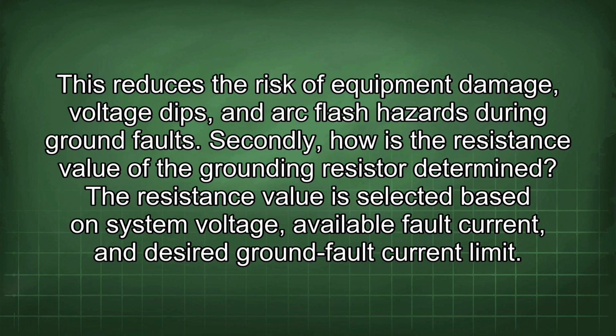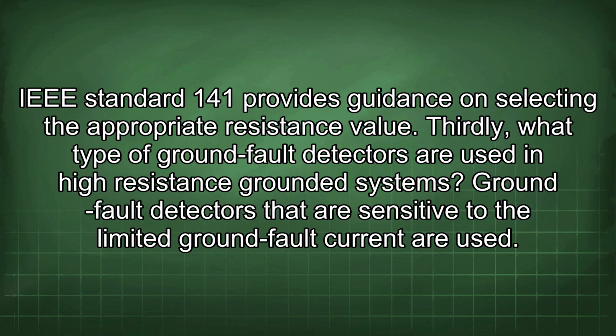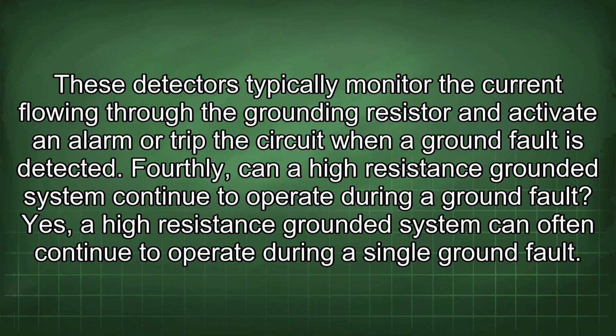Secondly, how is the resistance value of the grounding resistor determined? The resistance value is selected based on system voltage, available fault current, and desired ground fault current limit. IEEE Standard 141 provides guidance on selecting the appropriate resistance value. Thirdly, what type of ground fault detectors are used in high resistance grounded systems? Ground fault detectors that are sensitive to the limited ground fault current are used. These detectors typically monitor the current flowing through the grounding resistor and activate an alarm or trip the circuit when a ground fault is detected.